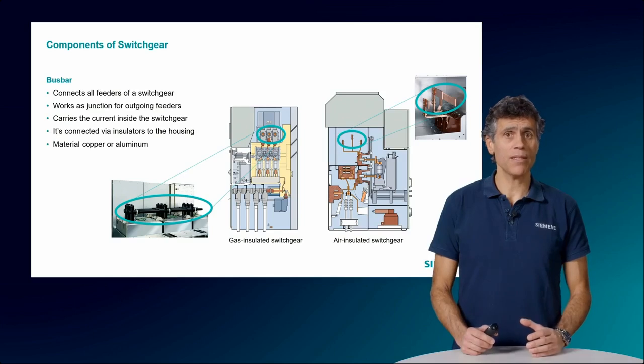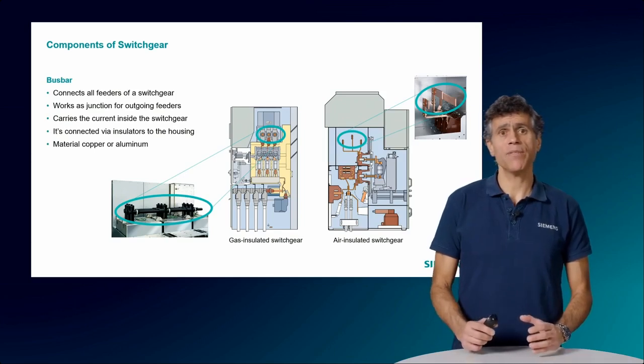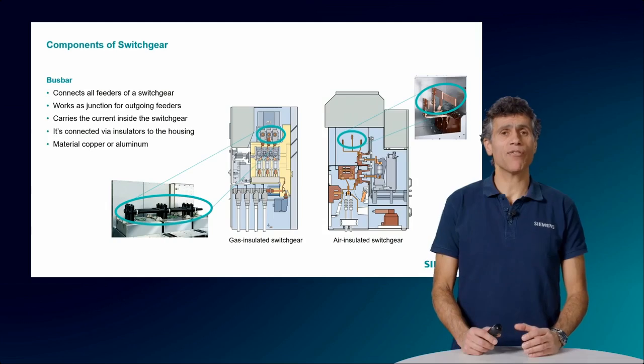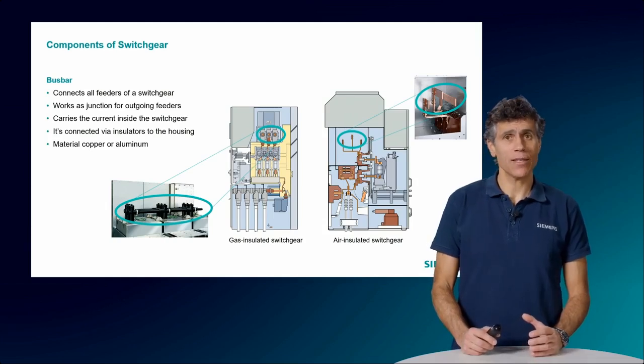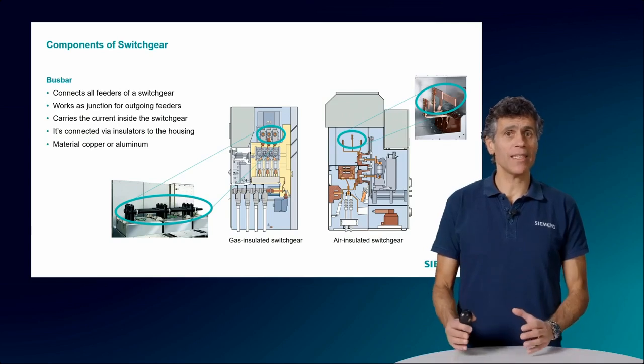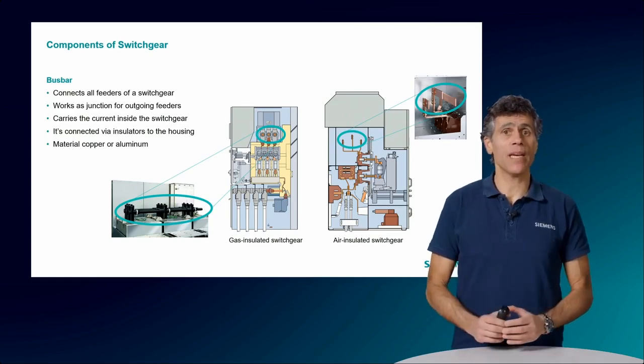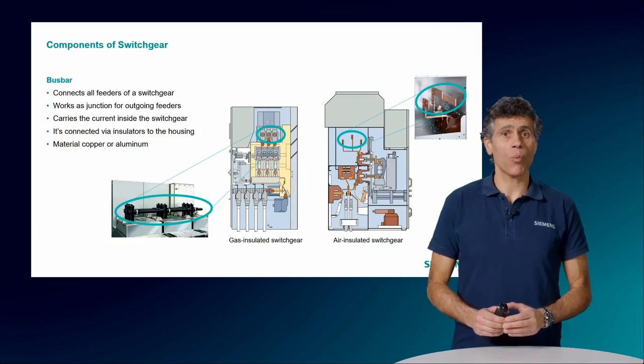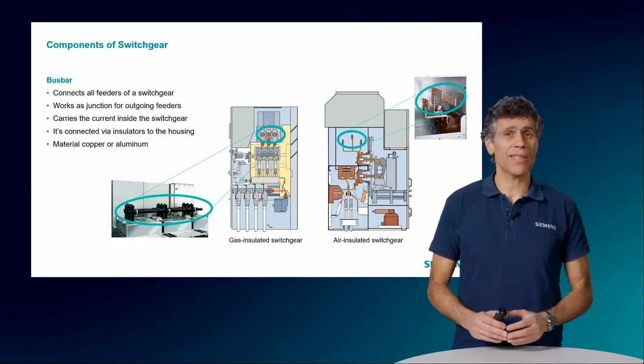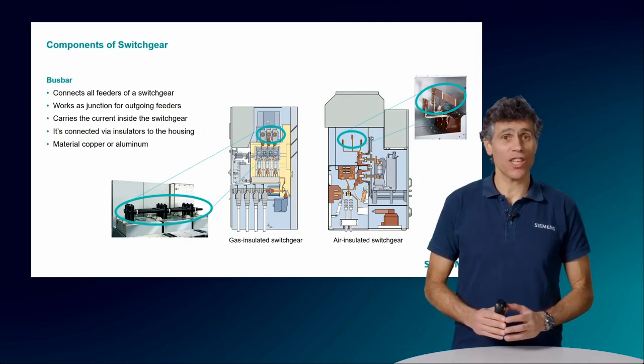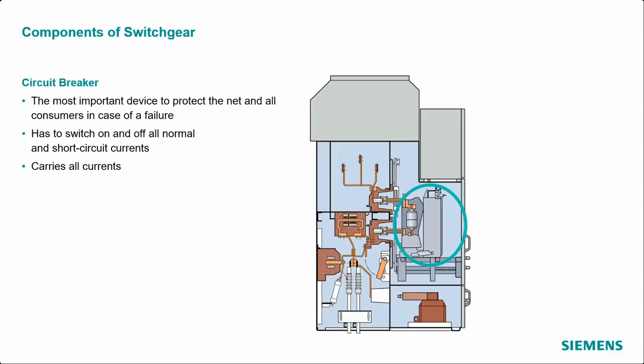The bars themselves behave as very strong magnets attracting each other. On one hand, the busbar must bend, not break, but on the other hand, it must be kept firmly fixed to be able to perform its function. When you see all these copper bars, you may think it's just copper, but building a busbar is in fact a big technical challenge.